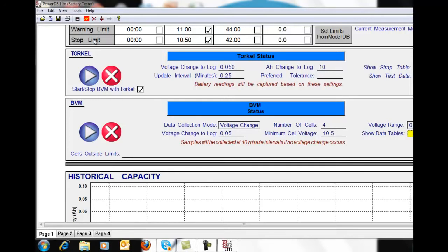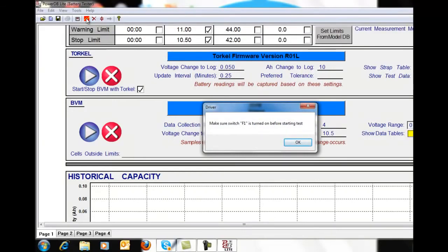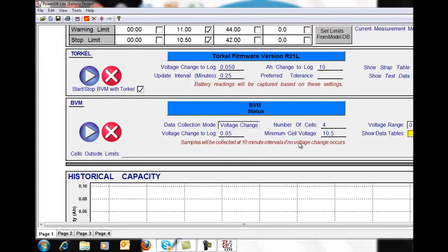Now, the first thing I'm going to do is come up to this little icon that says Initialize Instrument. It's the red box with the yellow lightning bolt. I'm going to initialize the equipment and actually communicate out, make sure that my communication ports are set properly. It's going to prompt me and say, did you remember to hit the F1 switch on the Torkel? We had done that earlier, so I will say OK. And at this point, I'm going to go ahead and start the test.